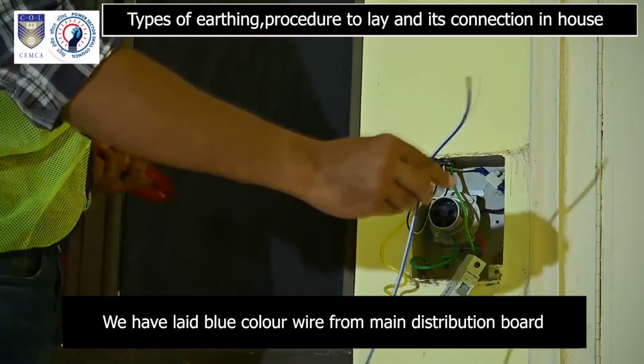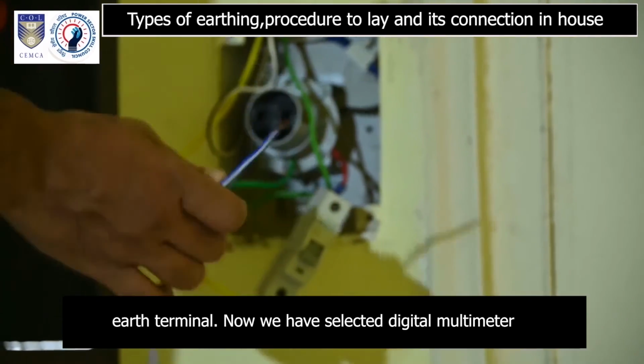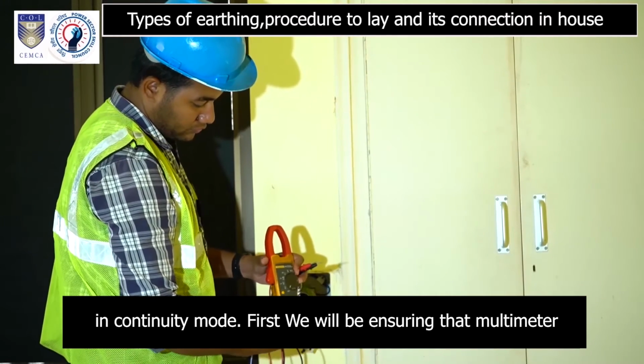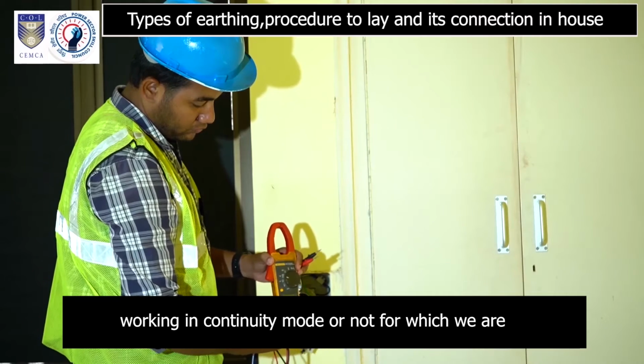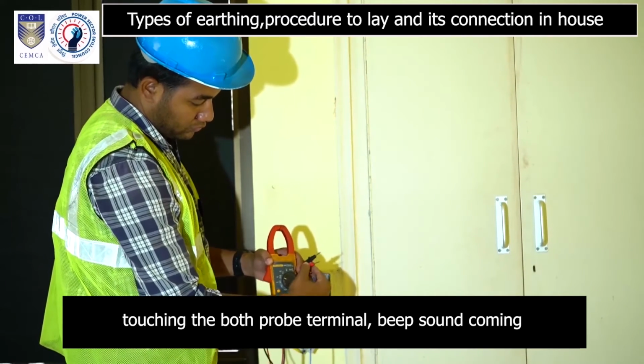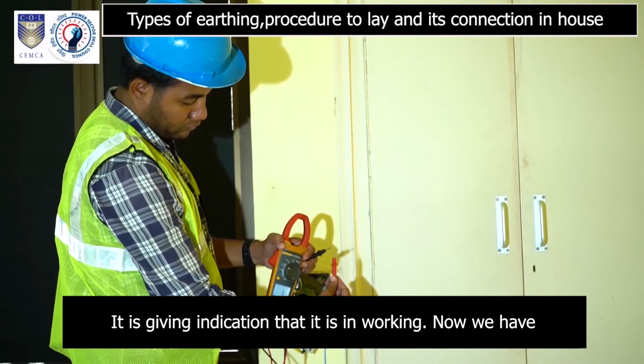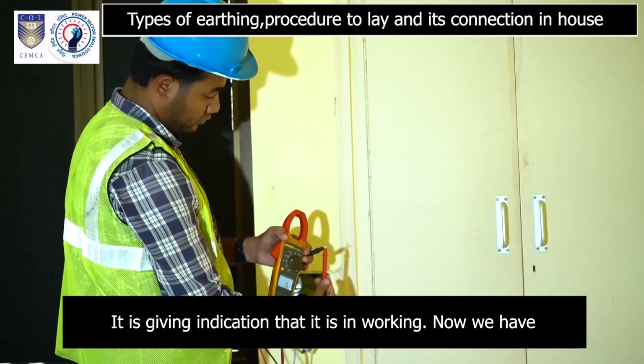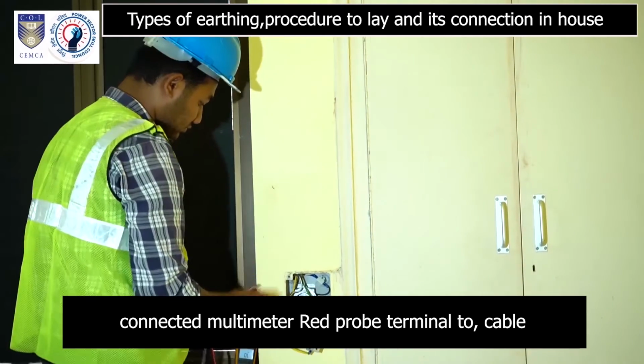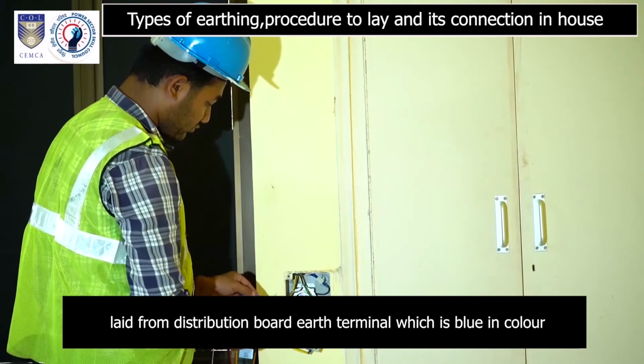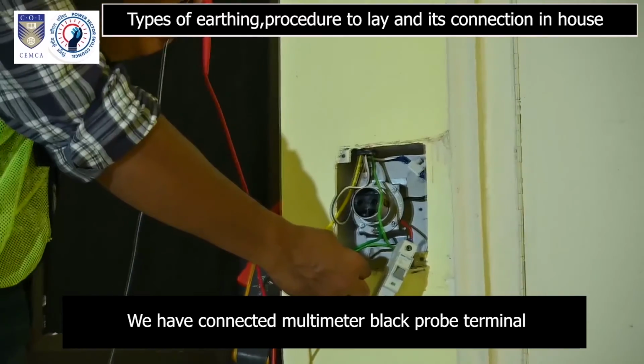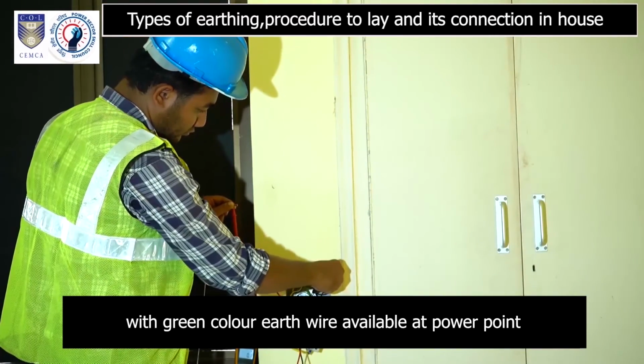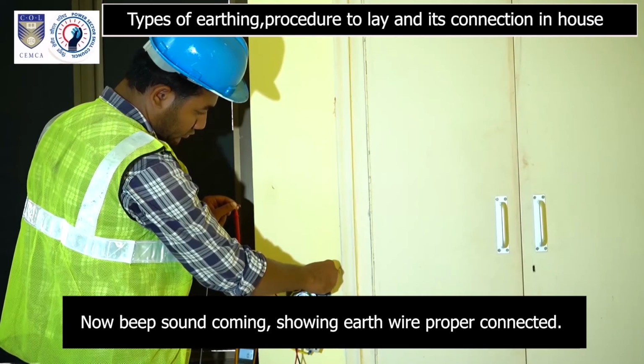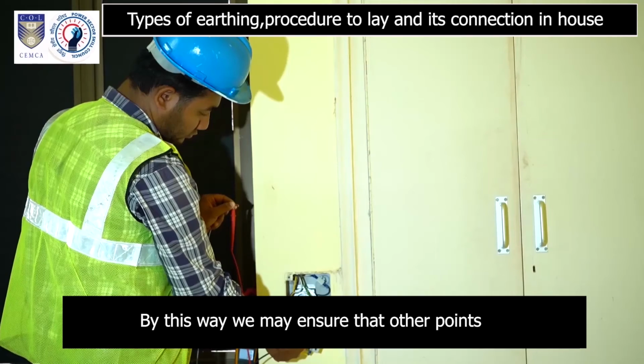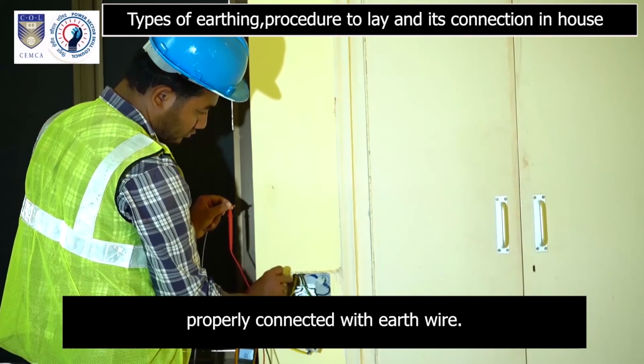For continuity test of earthing from the distribution board, we have laid a blue color wire from the main distribution board earth terminal. Now we have selected the digital multimeter in continuity mode. First we will ensure that the multimeter is working in continuity mode or not, for which we are touching both probe terminals. Beep sound coming. It is giving indication that it is working. Now we have connected the multimeter red probe terminal to the cable laid from the distribution board earth terminal, which is blue in color. We have connected the multimeter black probe terminal with the green color earth wire available at the power point. Now beep sound coming, showing earth wire properly connected. In this way, we may ensure that other points are properly connected with earth wire.